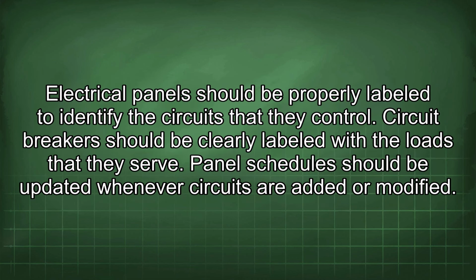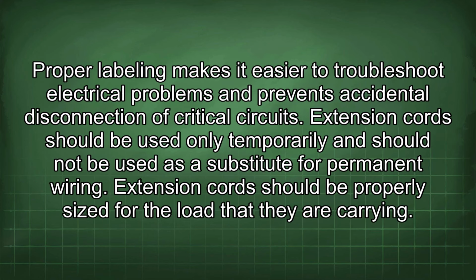Electrical panels should be properly labeled to identify the circuits that they control. Circuit breakers should be clearly labeled with the loads that they serve. Panel schedules should be updated whenever circuits are added or modified. Proper labeling makes it easier to troubleshoot electrical problems and prevents accidental disconnection of critical circuits.